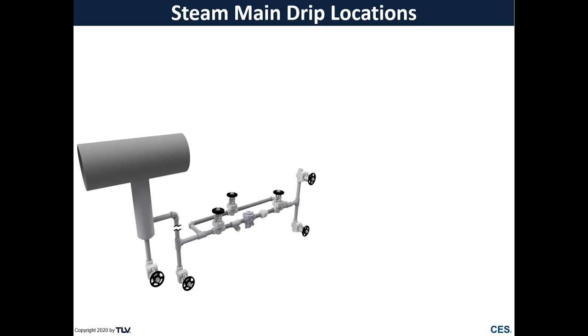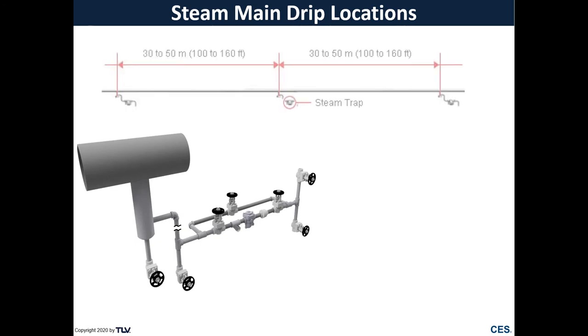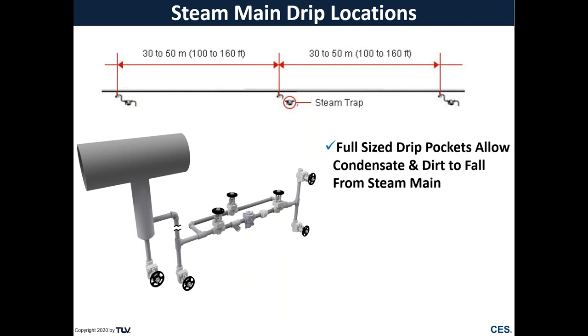So first we'll start off with steam mains and our drip pocket locations. So this is a typical drip pocket with a condensate discharge location. And we're generally going to want to see a drip pocket on a steam main about every 100 to 150 feet in order to drain out any condensate that is going to form due to radiant heat loss of our steam distribution piping.